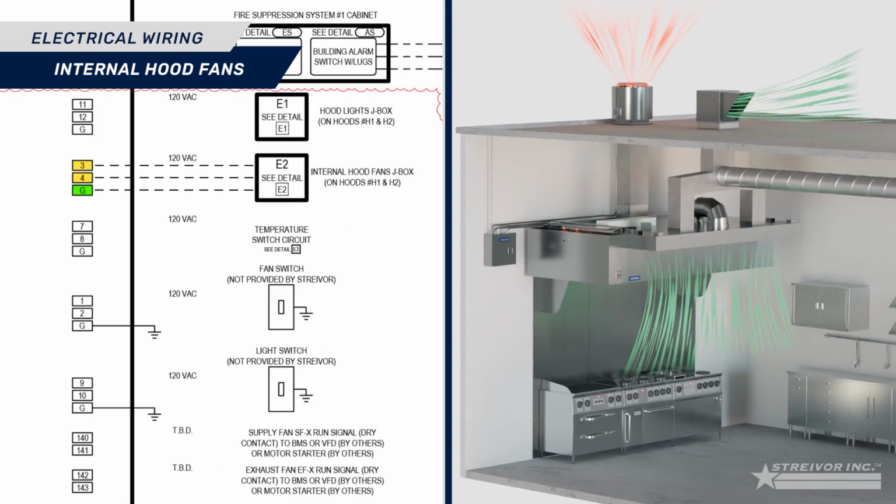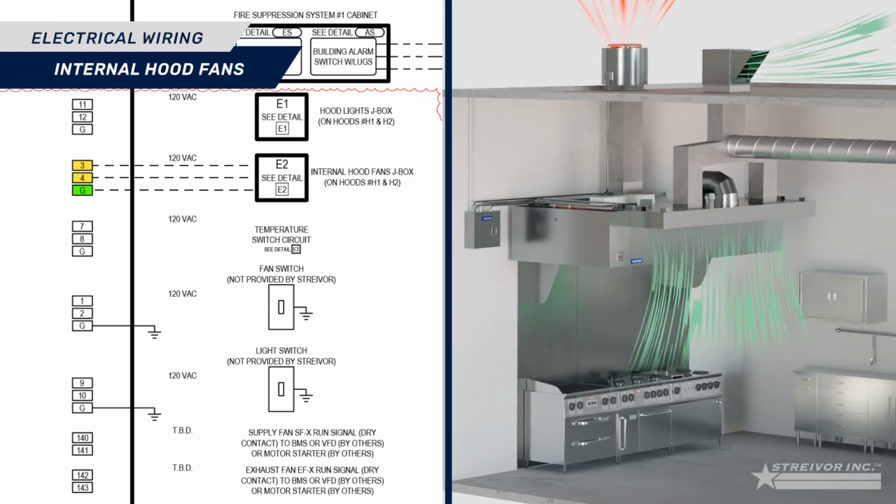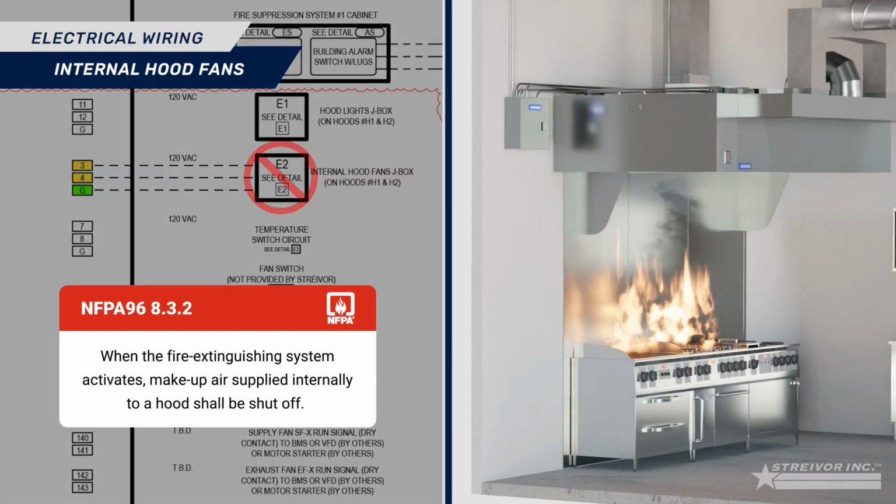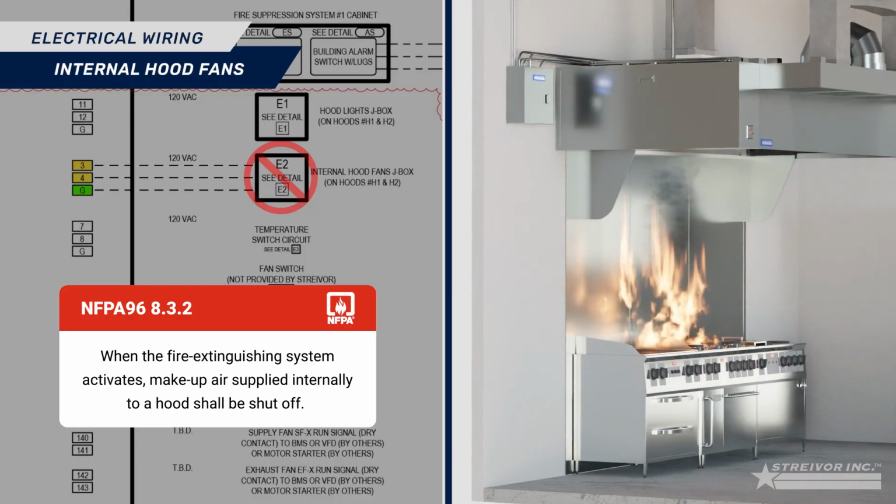Internal hood fan power to terminal blocks 3 and 4 will be automatically shunt during a fire suppression system activation to comply with NFPA 96 Section 8.3.2.